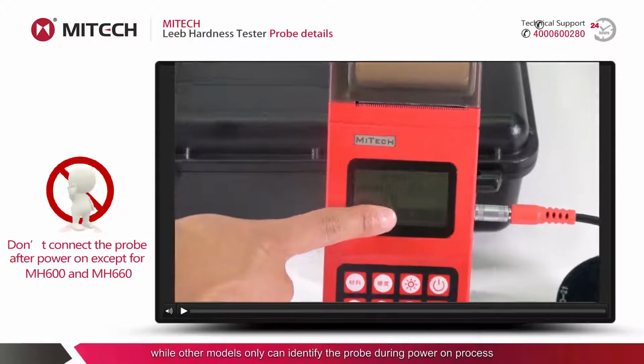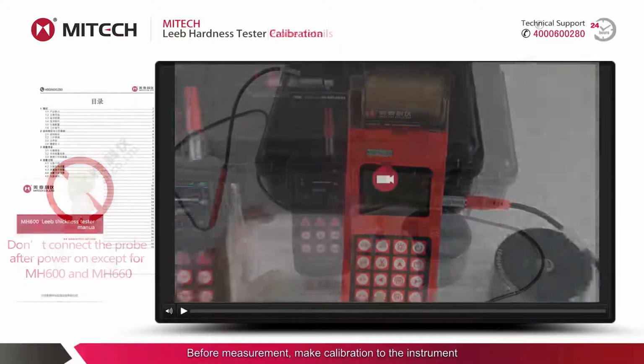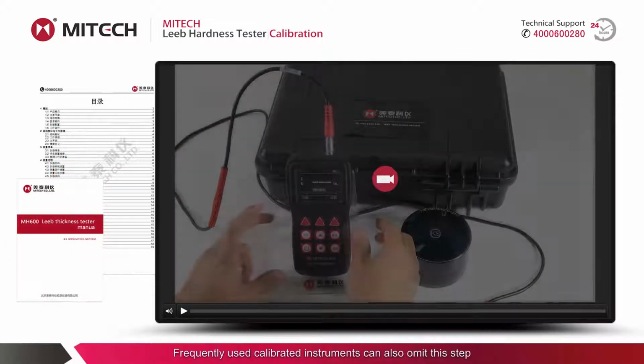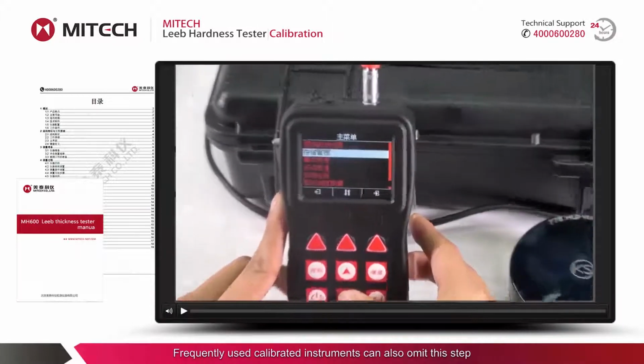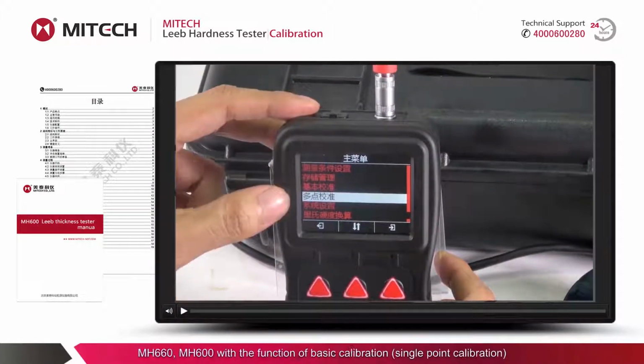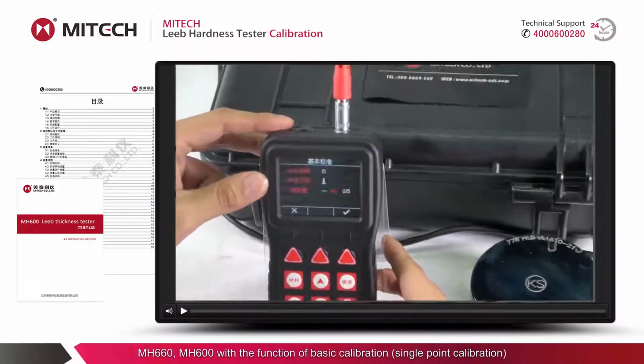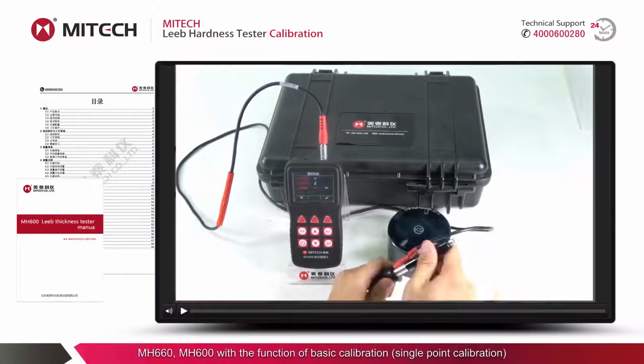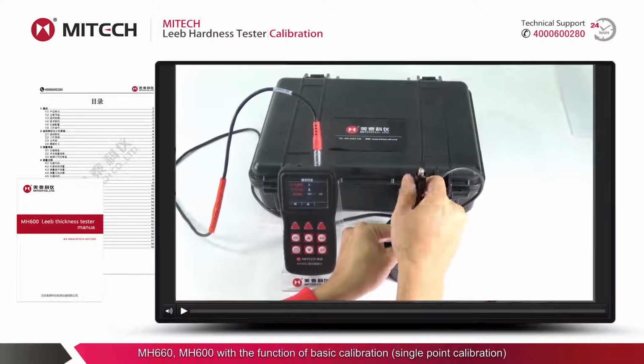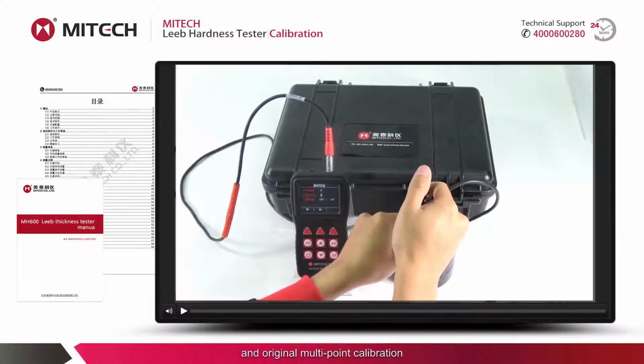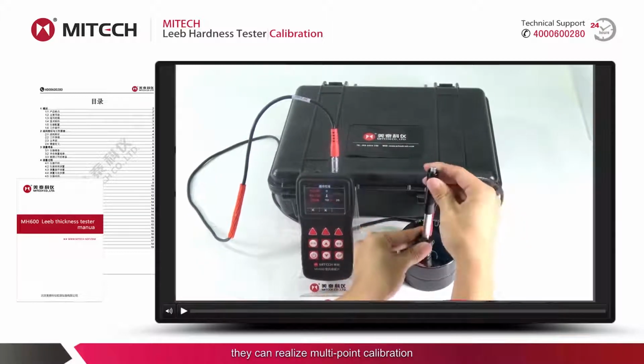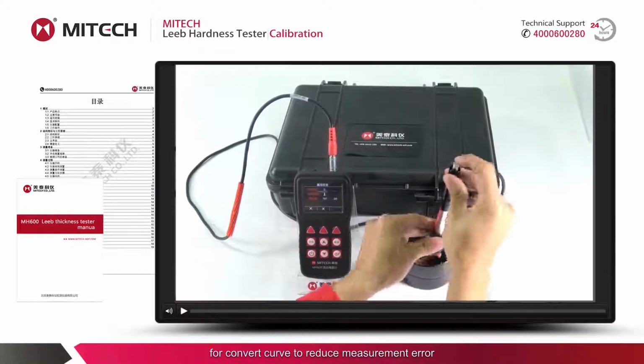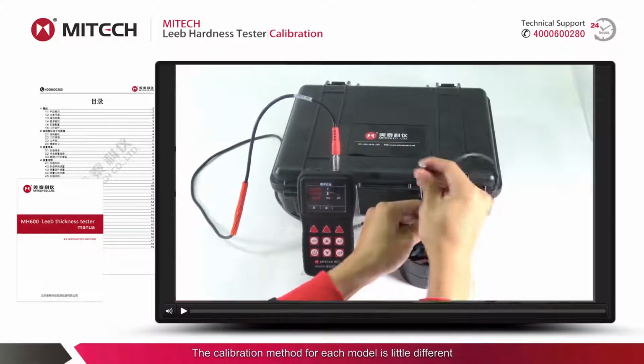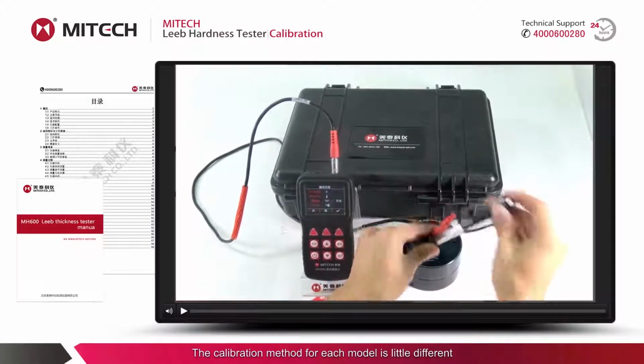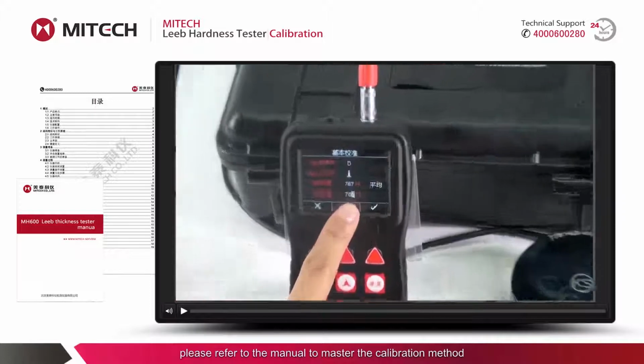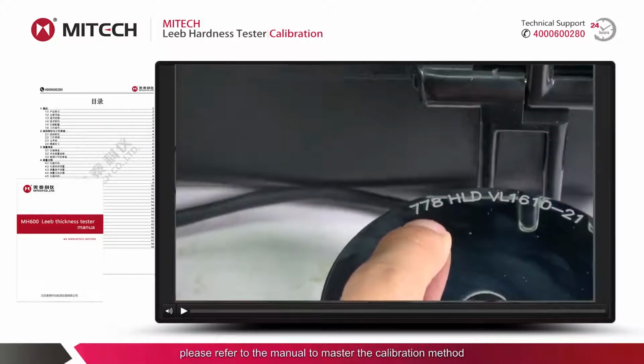during the power on process. Before measurement, calibrate the instrument. Frequently used calibrated instruments can also omit this step. MH660 and MH600 have the functions of basic calibration, single-point calibration, and original multi-point calibration. They can realize multi-point calibration for the convert curve to reduce measurement error. The calibration method for each model is a little different. Please refer to the manual to master the calibration method.